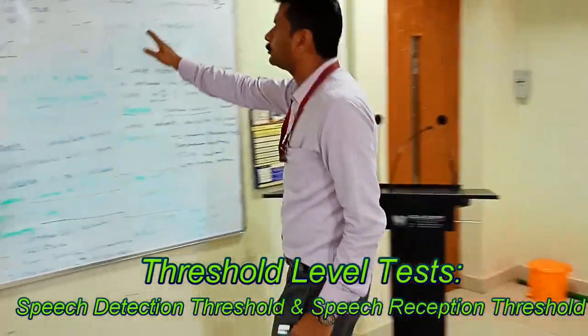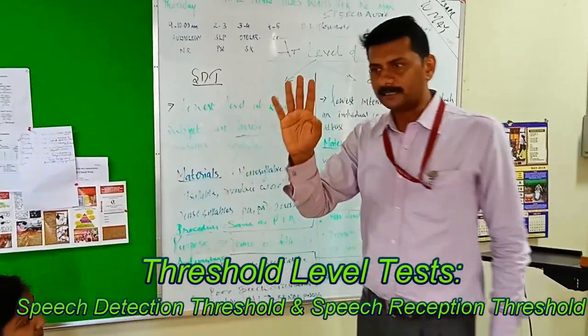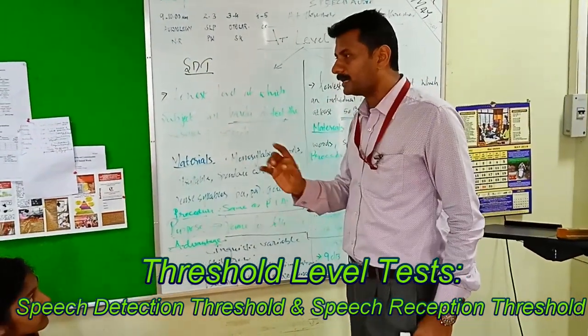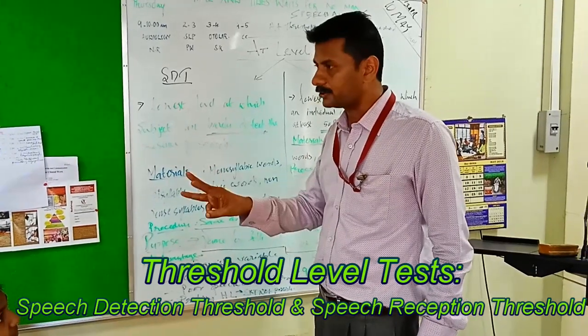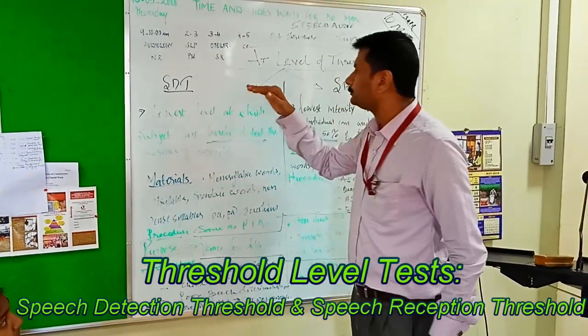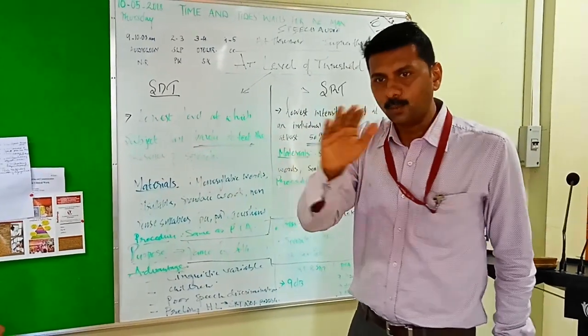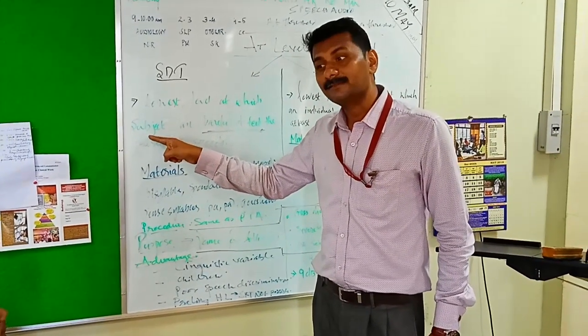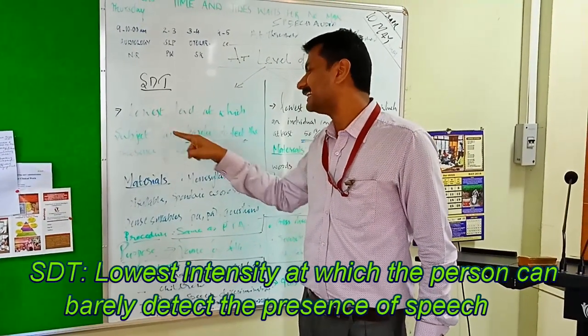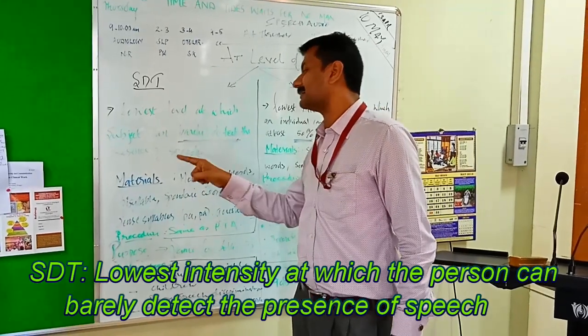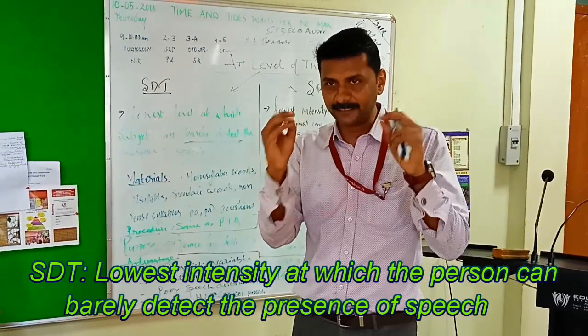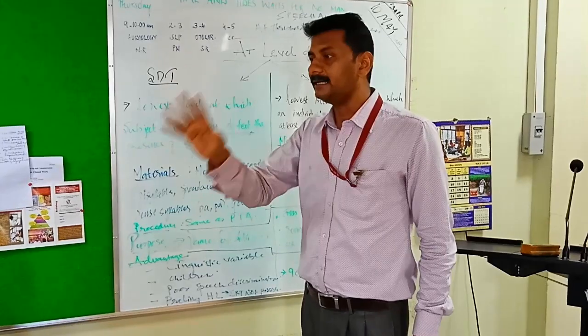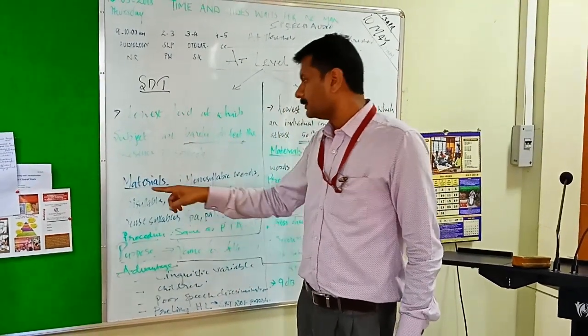The two tests are SDT — Speech Detection Threshold — and SRT, also known as Speech Reception Threshold. SDT is detection, which means the lowest level at which the person — the subject — can barely detect the presence of speech. We are using a speech stimulus and the person says 'yes, I can detect it.' They need not respond verbally.